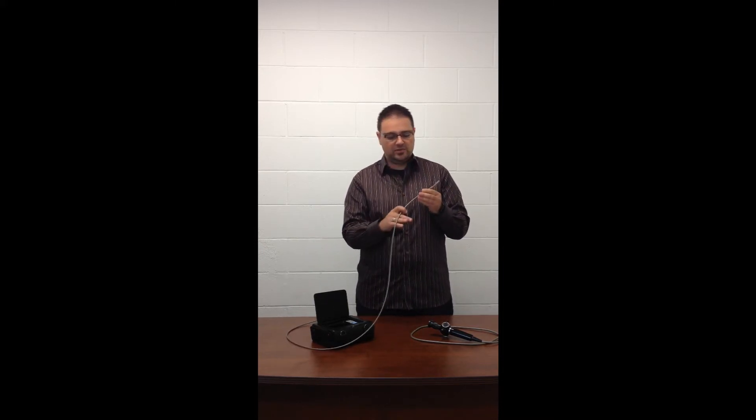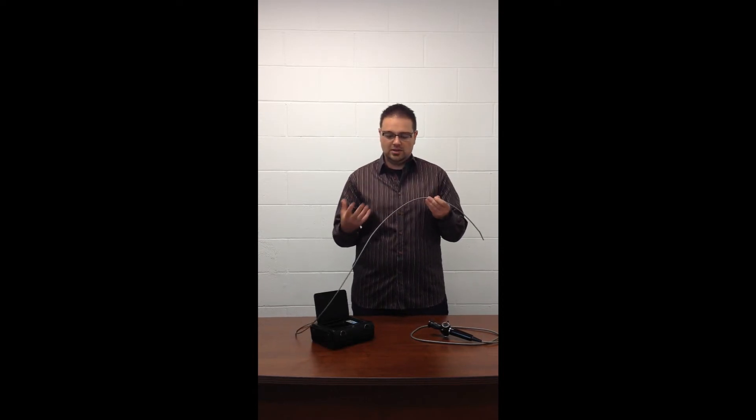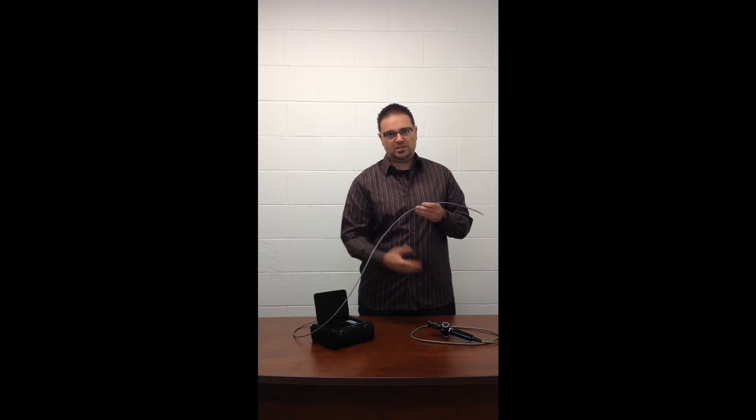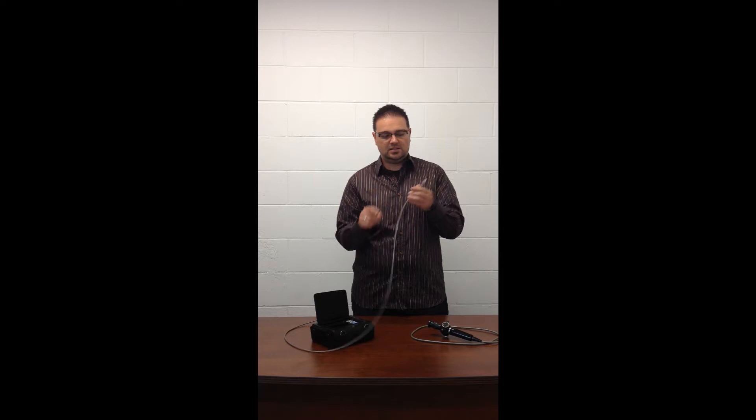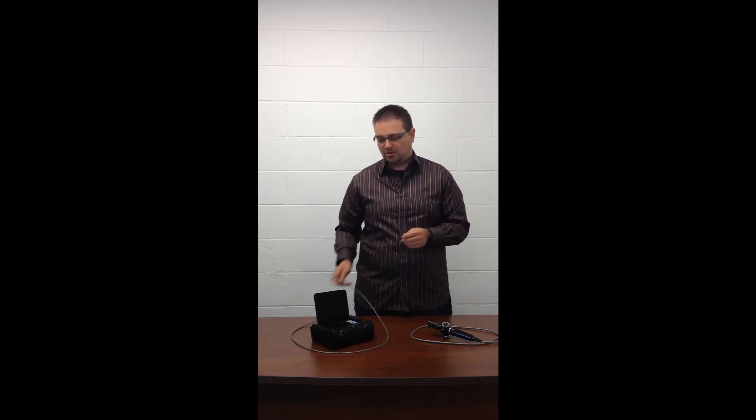And then the power for the LED lights as well. So if you damage this cable, not as bad as damaging this one because you don't have optics running through here. You pretty much just have power cables, but at the same time the video camera chip in the head of the probe is very expensive. And so if you damage the camera head and it needs to be replaced, you pretty much have to take apart the whole unit.